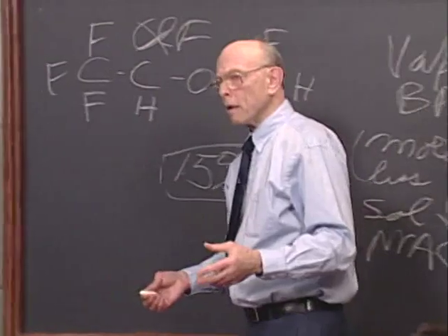How can we get drying of the absorbent? How can that be? It's sitting in that closed container. Let's see, who haven't we called on? Gentleman with the orange tie. Well, you get drying of the absorbent if you have high gas flow rates touching the absorbent for an extended period of time. Right. So if you give an anesthetic, and at the end of the anesthetic you turn off the oxygen, there's no problem. But if you leave it on and you go away for the weekend, there may be a problem. What else do you have to do besides leave the flow on in order to get drying? Well, there has to be actual contact with the absorbent by the flows.